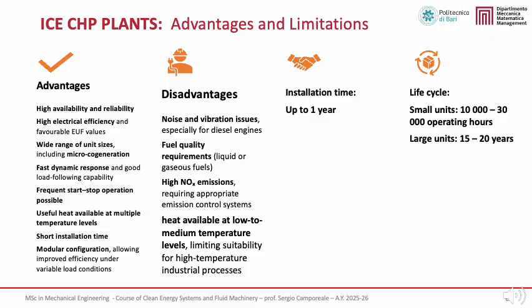Among the key advantages, ICE CHP systems offer high availability and reliability, high electrical efficiency with favorable EUF values, and a wide range of unit sizes, including micro-cogeneration. They are characterized by a fast, dynamic response, good load-following capability, and the possibility of frequent start-stop operation, which makes them well-suited to variable demand profiles. Additional advantages include short installation times and modular configurations, allowing efficiency to be maintained even under partial load operation.